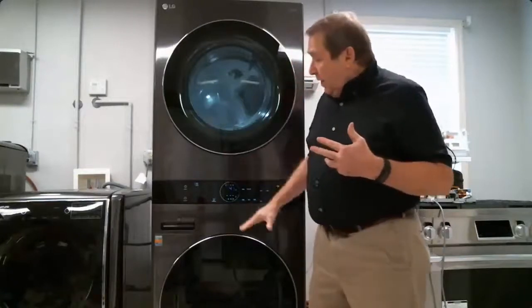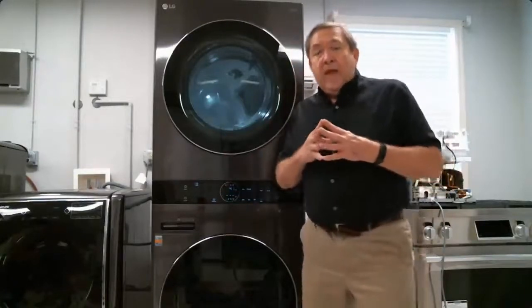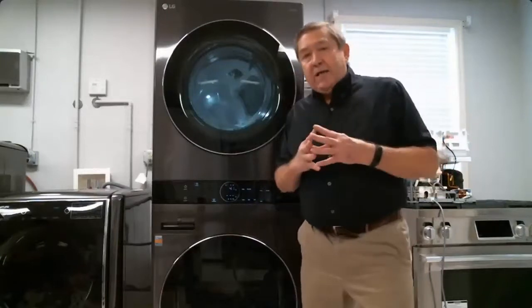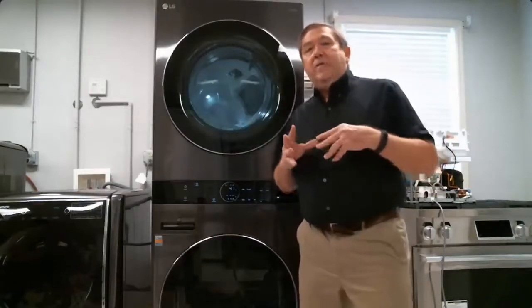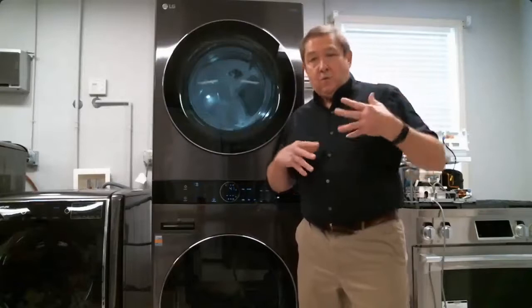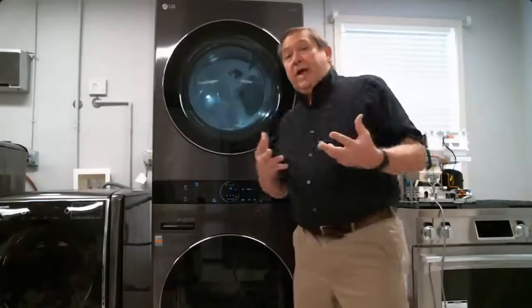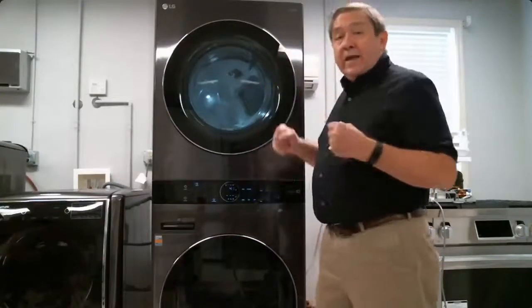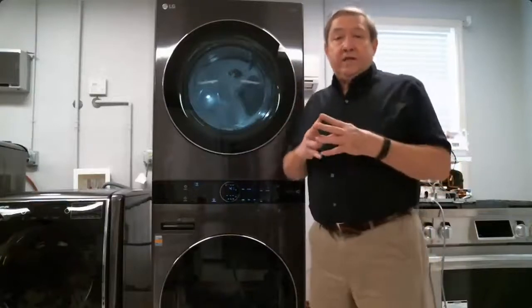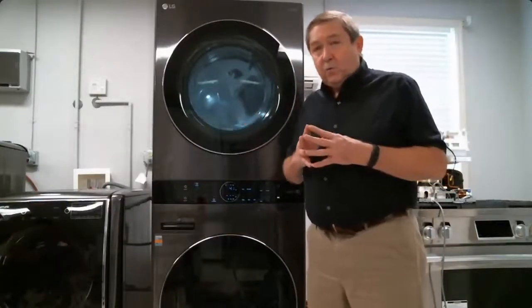I'll give you a quick rundown on how it works. It's looking at the temperature rise in your duct outlet, typically looking for a 65-degree temperature rise. So one thing you cannot do is run the install test while the dryer is hot—you're going to get false readings.